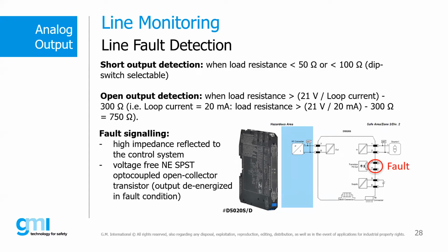There are two ways. The first involves the use of a fault contact which is opened when the fault is detected and sent to a digital input card of a dedicated DCS system. In addition, a LED on the barrier, typically red, is turned on. And the second method is the mirroring of the fault directly to the analog output card of the PLC, if the PLC card is compatible with this system and the supervised analog output card is able to detect a change in impedance at its input. This system allows us not to use a dedicated DCS and to save the costs related to it.